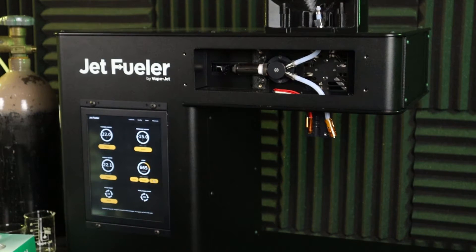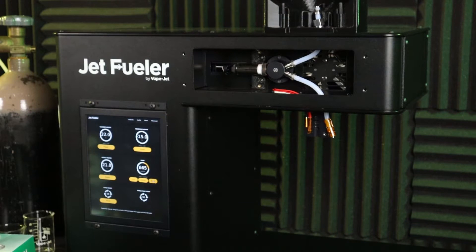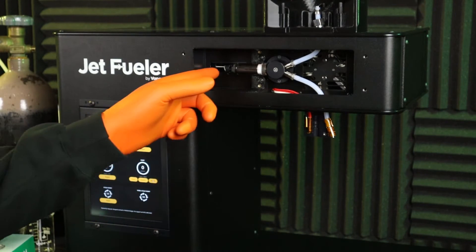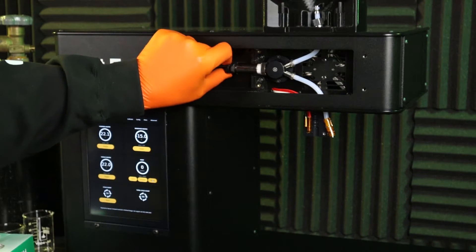With the syringe plunger key aligned to the pump translation stage, click reinitialize under the pump section of the advanced tab to move the pump translation stage into place at the rear of the syringe plunger. Reattach the thumb screw which secures the syringe plunger to the pump translation stage.